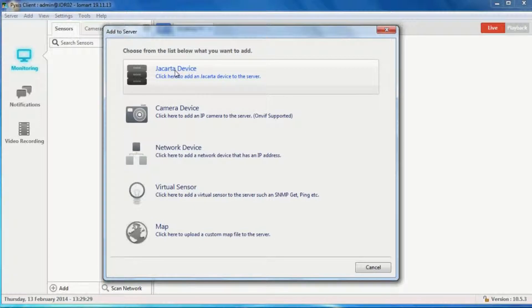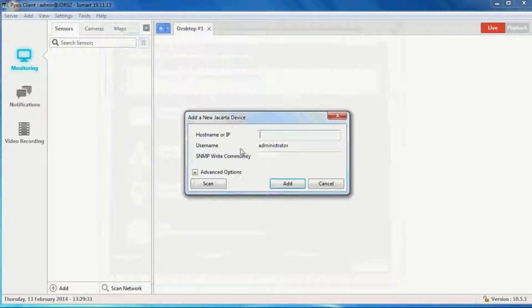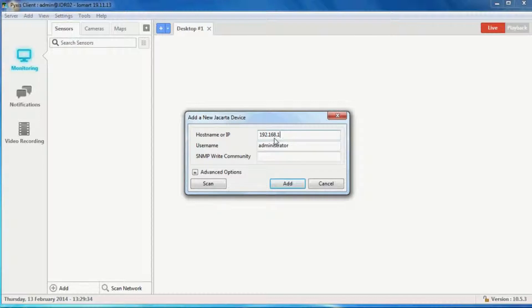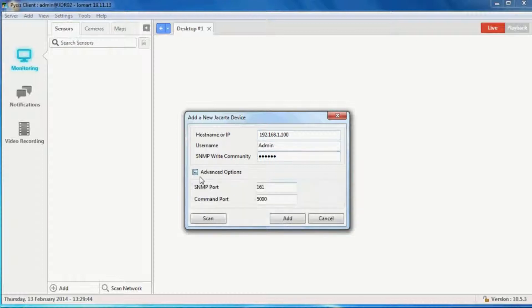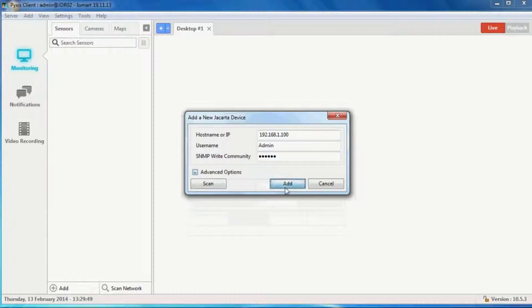I'm going to add a Jacarta device, which in this case means an iMeter. I put the IP address in, the admin username, and the read-write community string. In the advanced options I can change ports if needs be, but I'm just using the defaults.